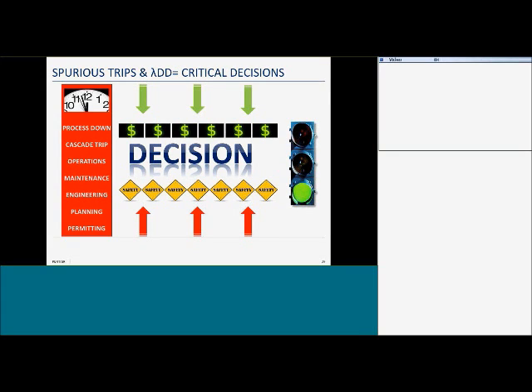which impacts the risk reduction factor. But number two, it's the most critical part of what they're going to do when it comes to spurious trips. They need to be able to diagnose what was the root cause of the spurious trip. And in addition to more diagnostic data, they need it to be credible data. So empowering this team of decision makers at the end user level, this is an area where we can get in and make a big difference.